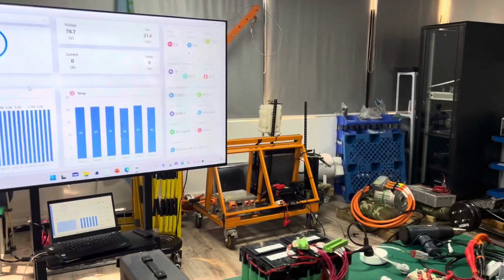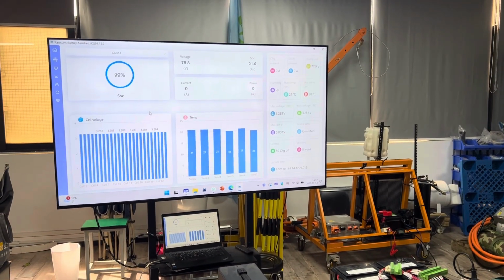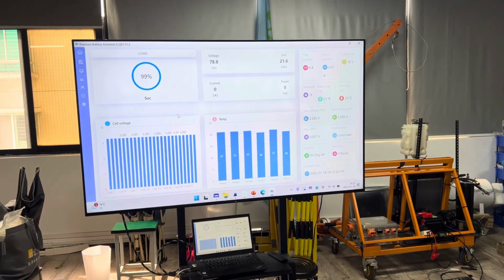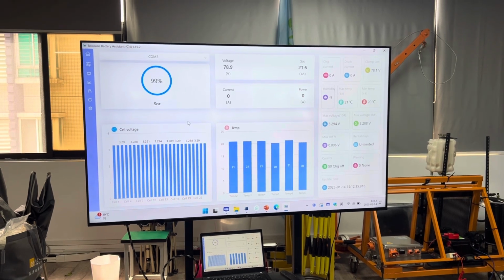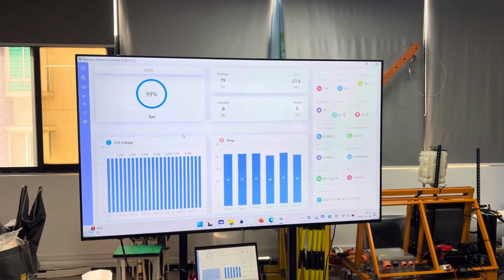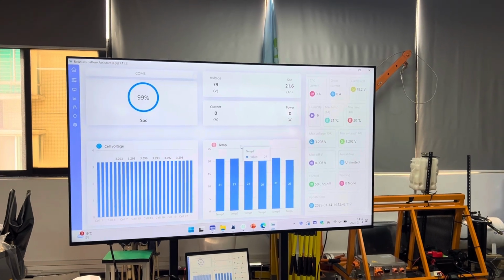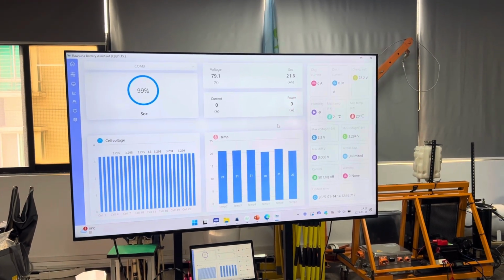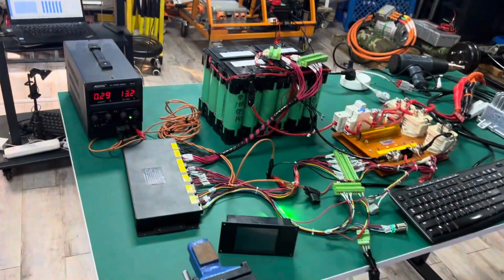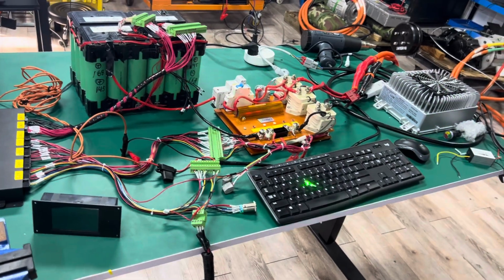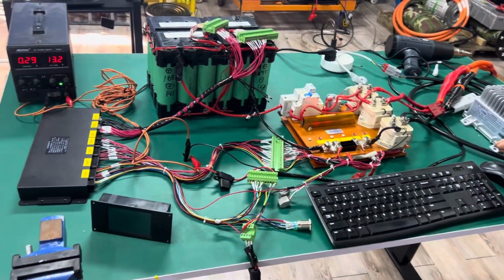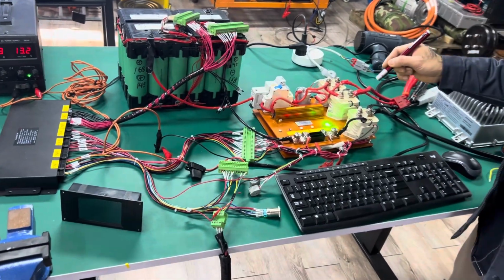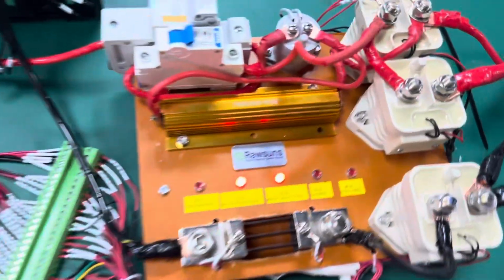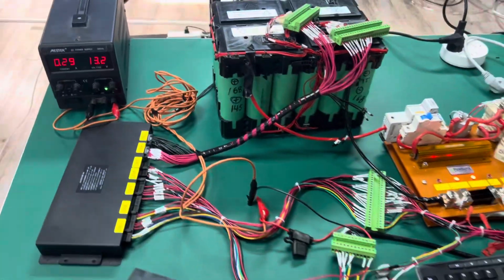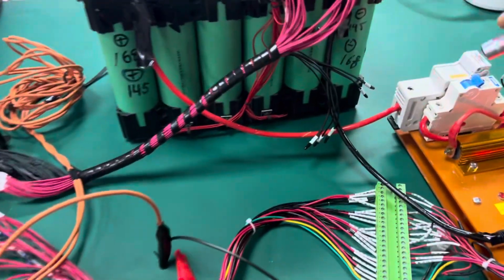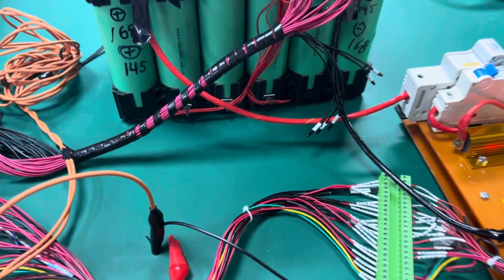Just now we can see the discharge current was more than 1C because this battery is 22 Ah. The maximum discharge current just reached 40 amps, so nearly around 2C discharge rate. This is the charging test and the discharge test of our BMS. Also the connection of our BMS, and in this BMS system we also have the cooling function. It means that when the temperature goes to a certain degree, the cooling will start.